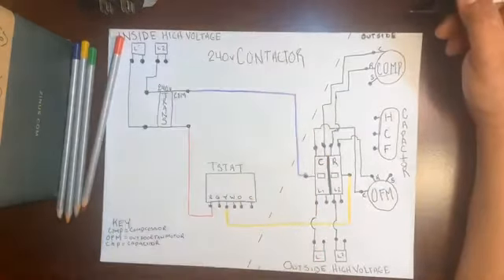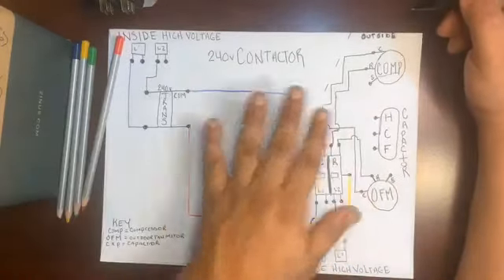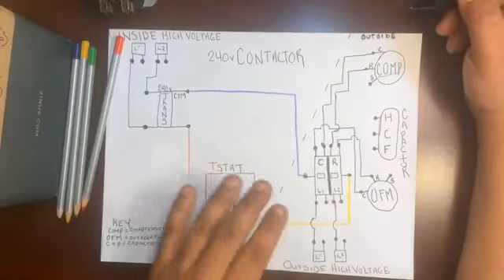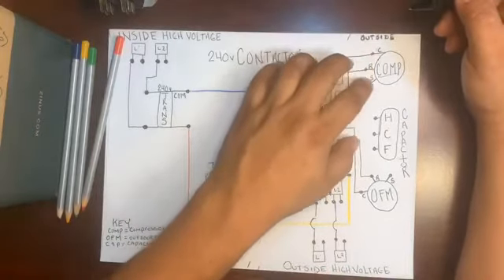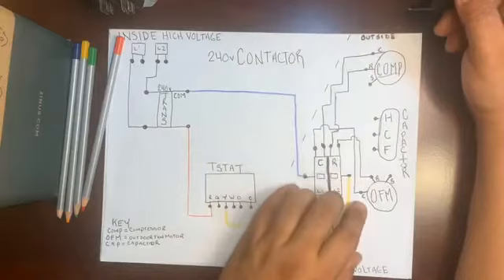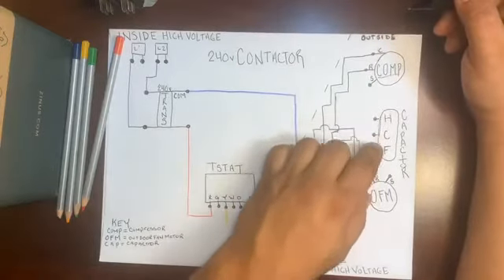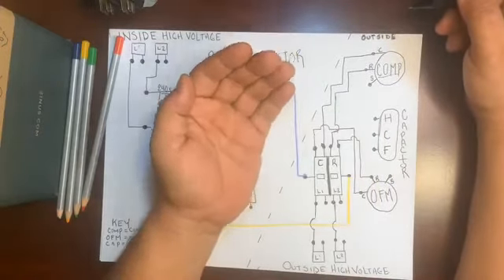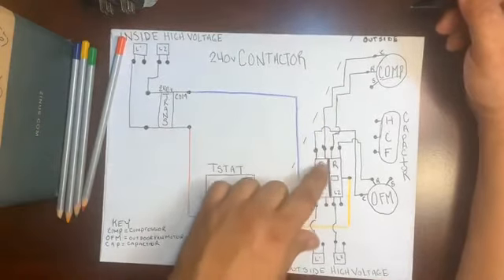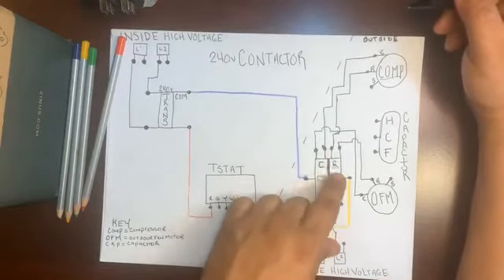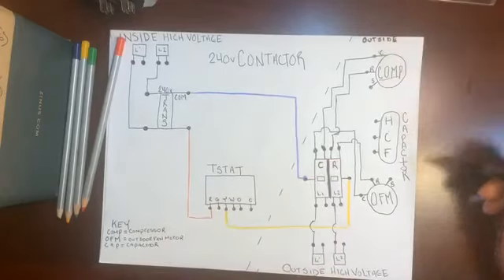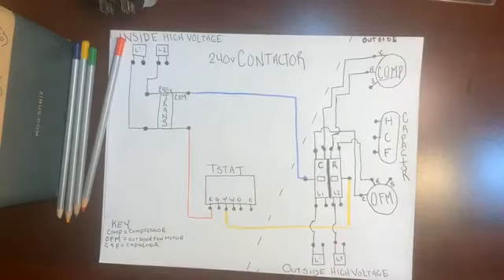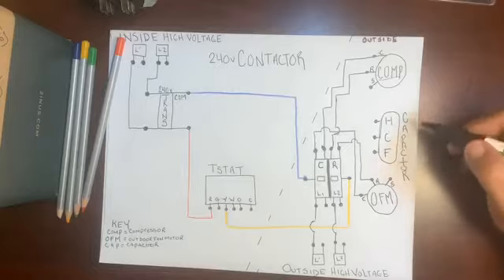If you want to be a service tech, you want to be able to fix an older machine, and you're not always going to have a wiring diagram. So you have to be able to identify what's common, run, and start on the compressor and the outdoor fan motor, and be able to replace a capacitor without even having the wiring diagram, because you know how everything connects into one common side of the contactor and one common side of the run side of the contactor. So let's go ahead and get our capacitor connected.